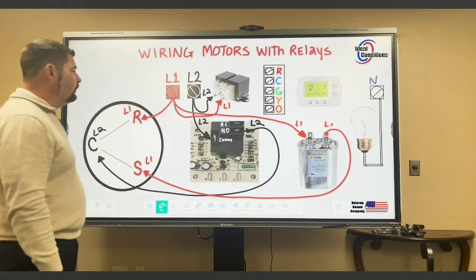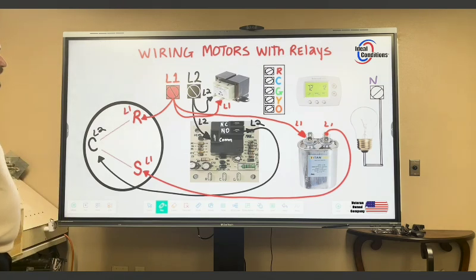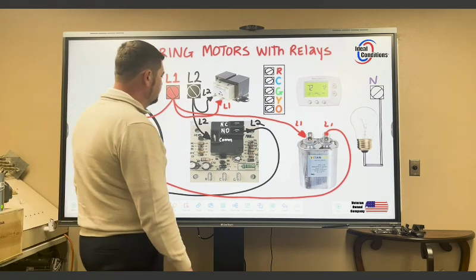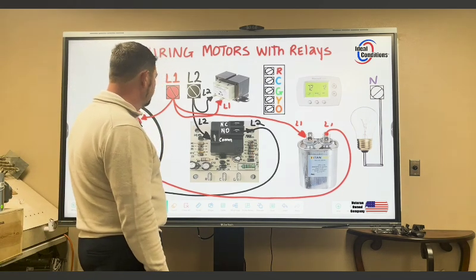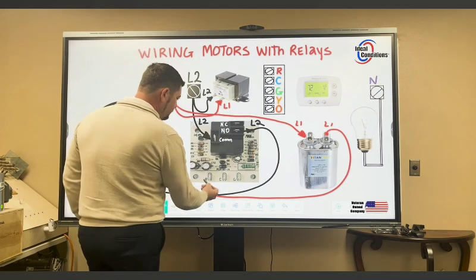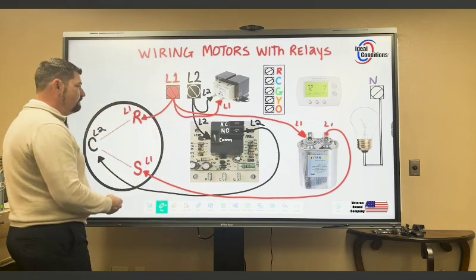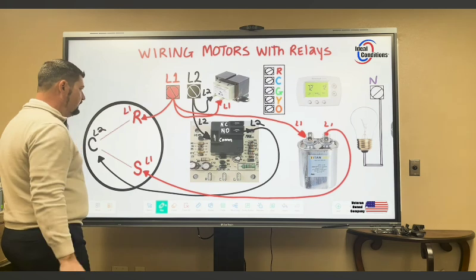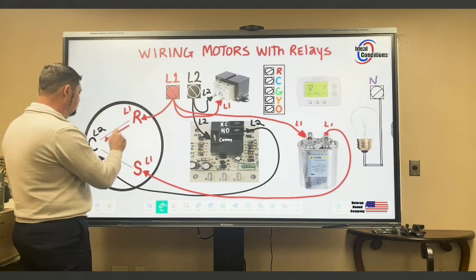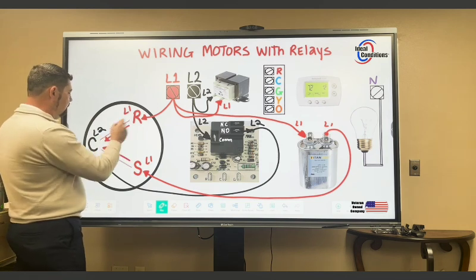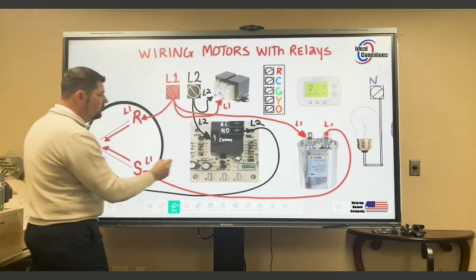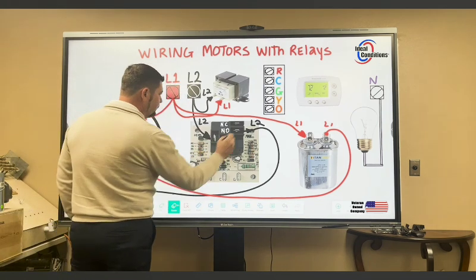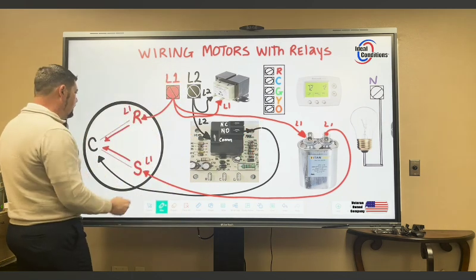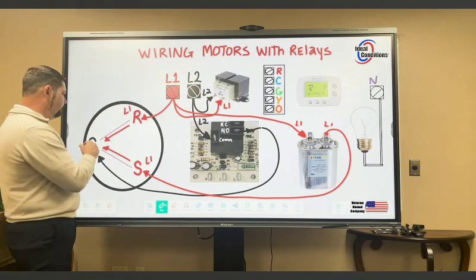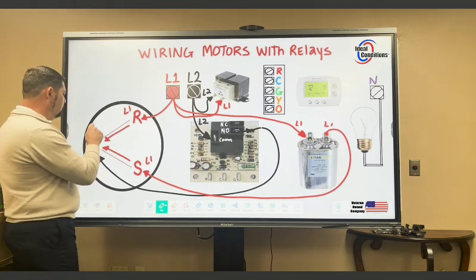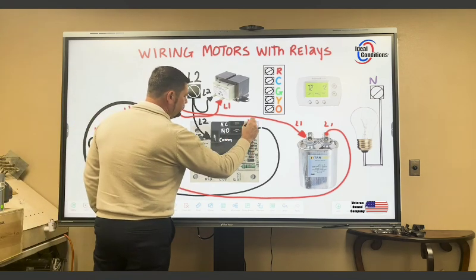Where else does L1 need to be present? We landed all our high voltage terminals. We didn't wire the light bulb yet, that's okay. But that's pretty much everywhere L1 and L2 need to be present. Now, because I don't have any voltage here yet, I'm still open. So if I want to look at where I am reading power, I'm not reading L2 here, and I'm not reading L2 here. Because of the path of electricity, that theory suggests that I'm actually reading L1 here. So we're going to go ahead and erase that value, and erase this other value here. And what we're going to do is write down the value that I would actually have there if I measured it with a meter. So this is going to be L1, and right now this is also going to be L1.